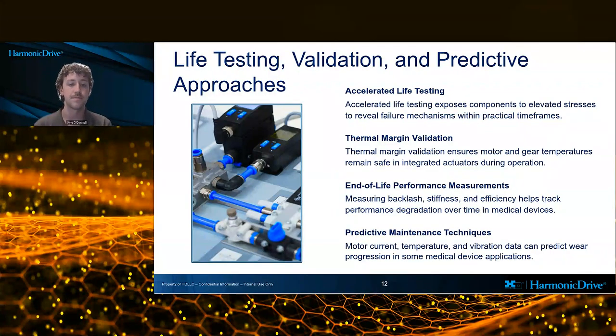your servo system. In some applications, predictive maintenance techniques may be feasible, using motor current, temperature, or vibration data to kind of infer the wear progression. While predictive maintenance is not always practical in sealed medical devices, designing components with predictable degradation behavior, like strain wave gears or harmonic drives, makes both the testing and interpretation of those results much more straightforward. Ultimately, robust validation builds confidence not only in the initial performance of a system, but in its long-term clinical reliability and viability.